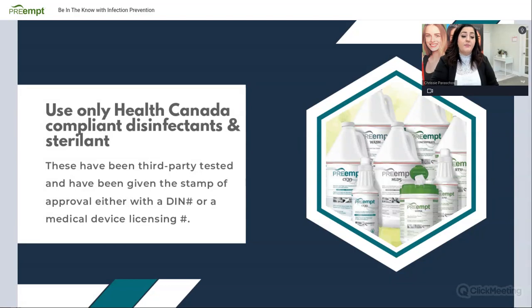Use only Health Canada compliant disinfectants and sterilants. The very important thing to know is that if you look at the label of your disinfectant and there's a DIN number on an intermediate level disinfectant, perfect. That's a drug identification number. It means it has gone through a third party, been tested for what that intermediate level disinfectant does and what it kills, and it's been stamped by Health Canada. Same thing with your high level disinfectants and your sterilants, although in 2018, I believe, they changed it from a DIN number to a medical device licensing number.